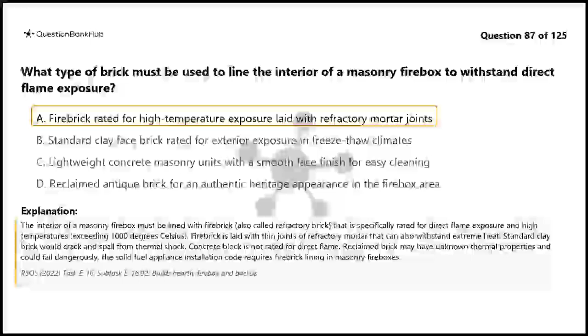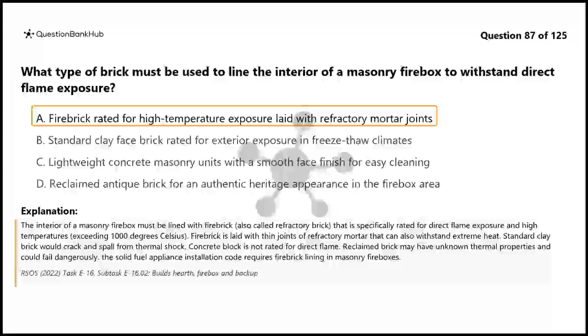Standard clay brick would crack and spall from thermal shock. Concrete block is not rated for direct flame. Reclaimed brick may have unknown thermal properties and could fail dangerously. The solid fuel appliance installation code requires fire brick lining in masonry fireboxes.